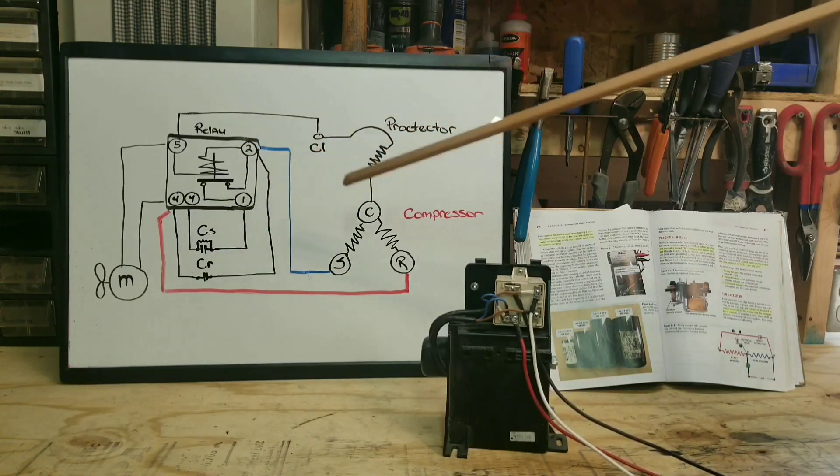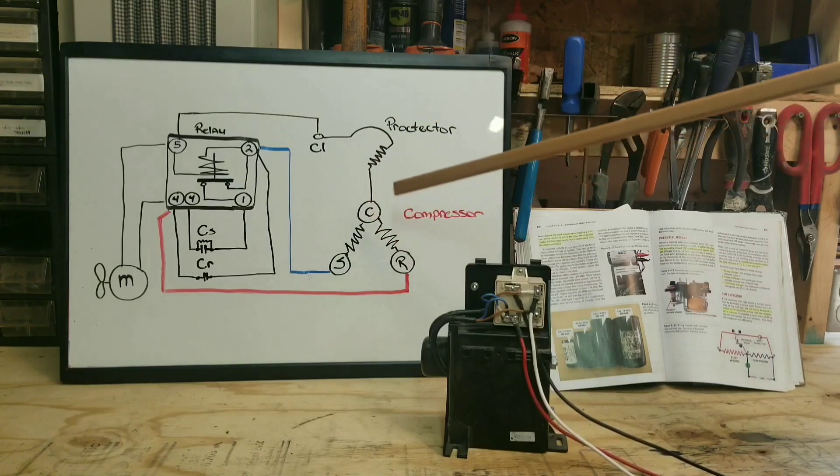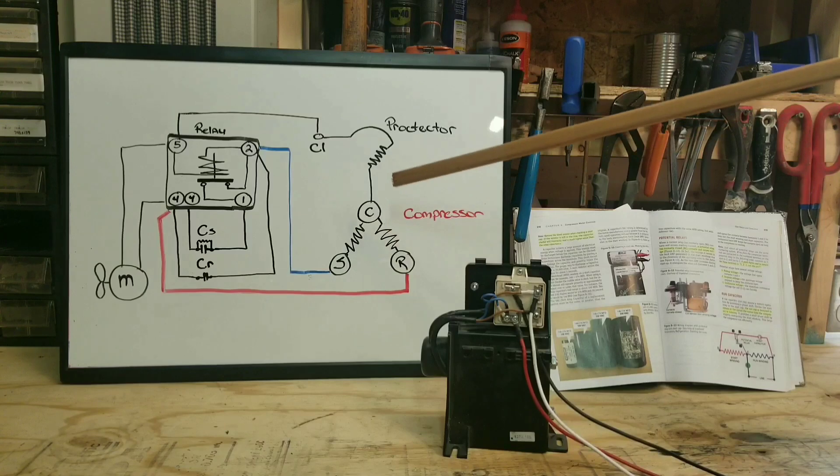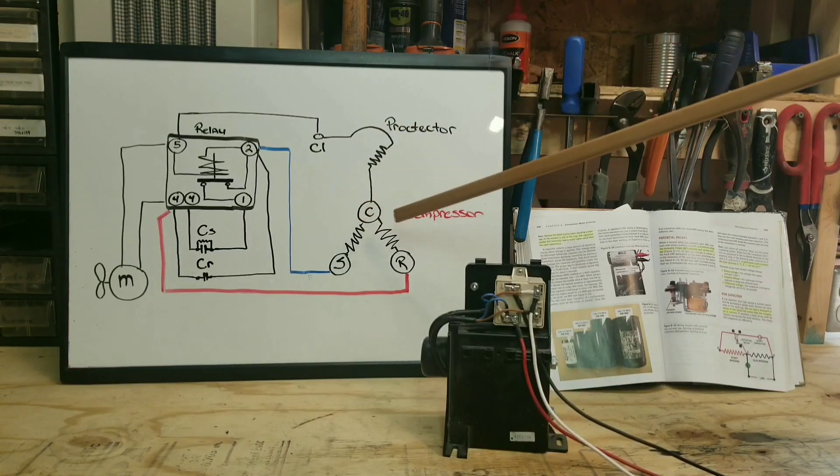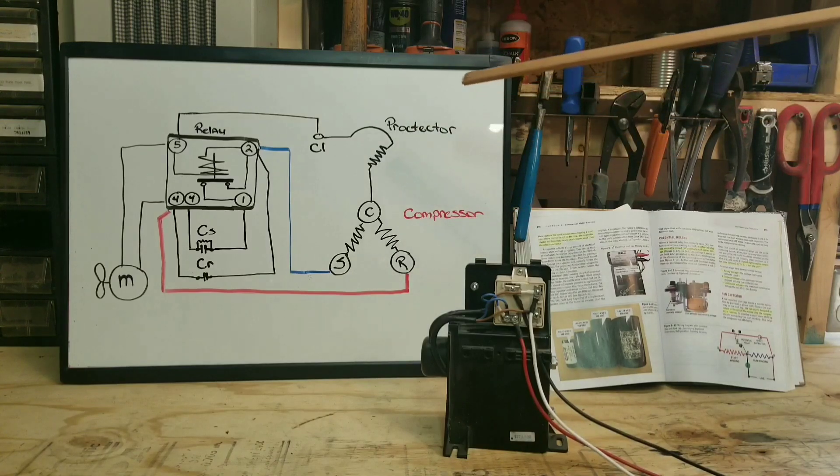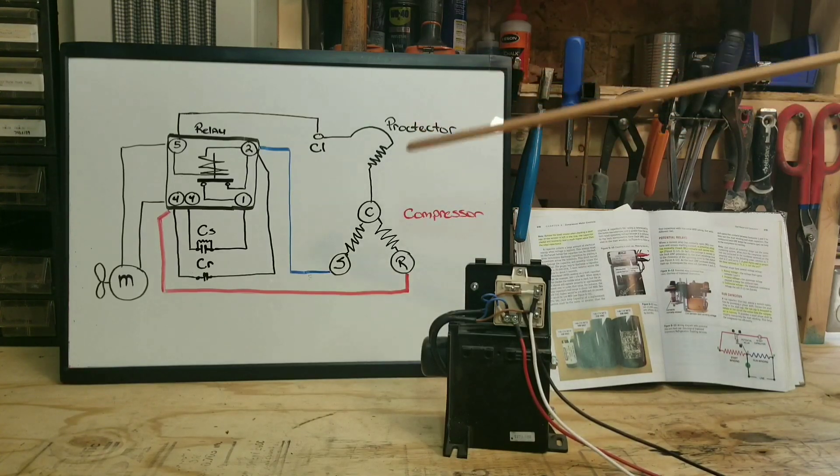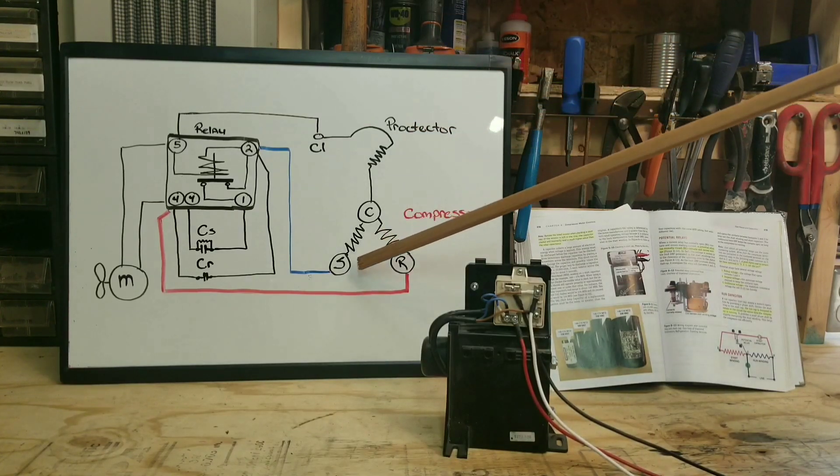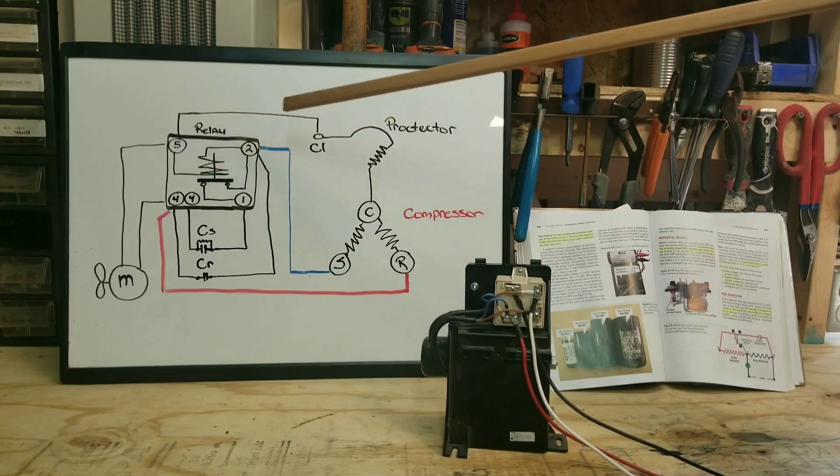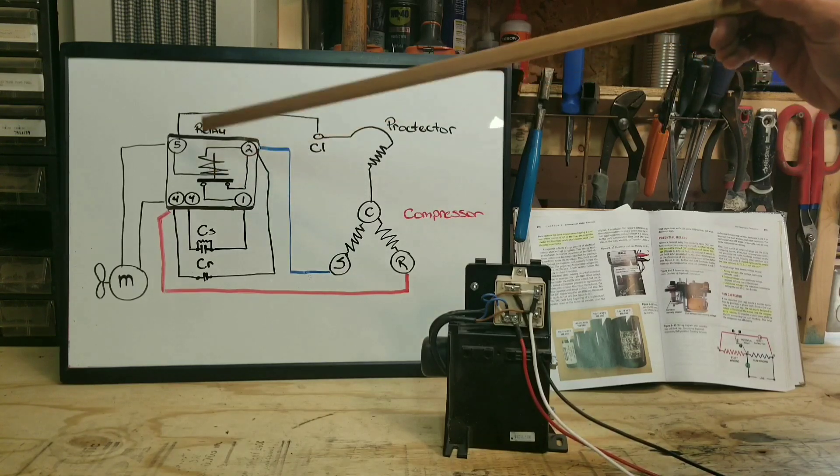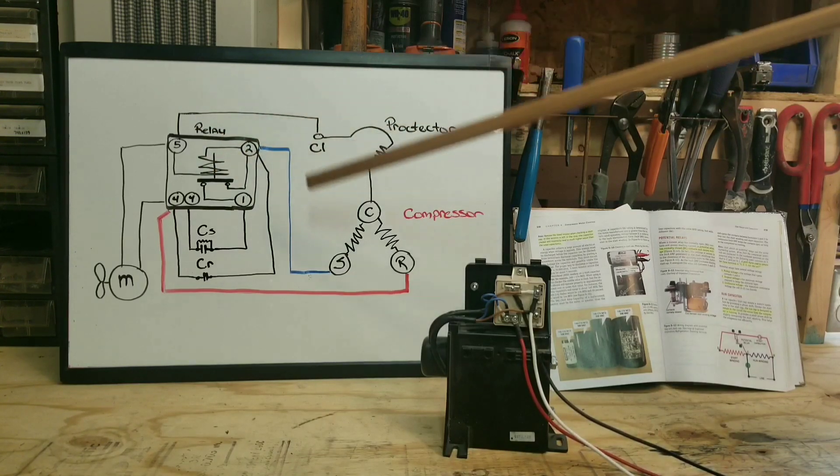Now the key part for me was thinking of this start winding as a generator. Once it's going, yes, you do need to apply power to that electric motor in order to get it to turn over, but once it is turning over, that electric motor also acts as a generator and it generates that back EMF that opens this up. So once that's opened up, it'll stay opened up as long as the compressor is running.